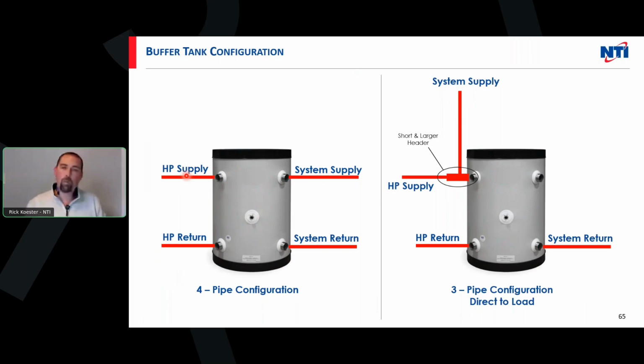It's going to blend this system down, right? So now it may not be the same water temps that I'm bringing in. It might take for that system to recover and get those proper temperatures. So if my system or my application is sensitive to the water temps I'm designing around, I may want to look at a 3-pipe compared to a 4-pipe. And again, as these applications come around and we have these conversations with contractors and then look at their system and look at what they're designing, we'll be able to make those recommendations and help them with that.